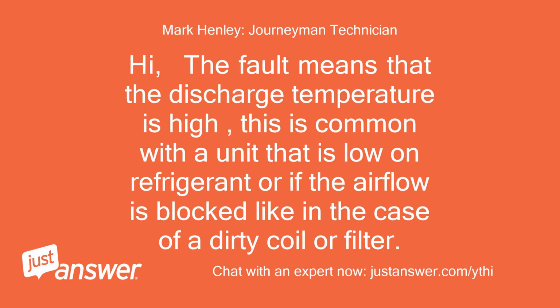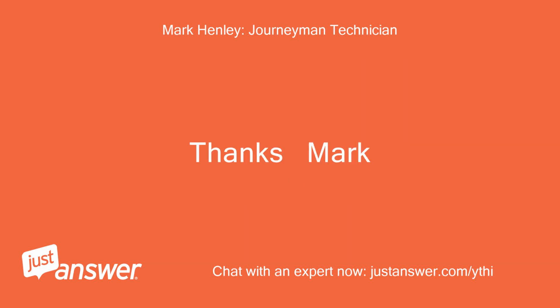Hi, the fault means that the discharge temperature is high. This is common with a unit that is low on refrigerant or if the airflow is blocked, like in the case of a dirty coil or filter. Thanks, Mark.